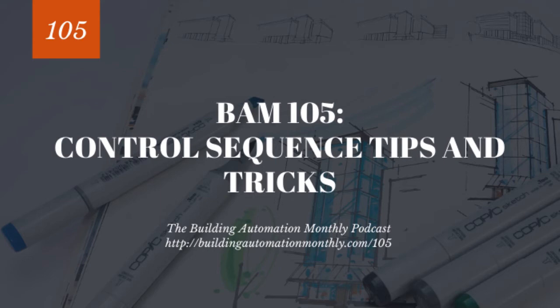However, with that being said, that is another reason why you would rearrange the sequence, but you're not changing the sequence. You're not changing the fact that you're enabling a chiller. An example of changing the sequence would be where you have an air handler whose discharge air temperature is reset maybe by box position. So you look at box position and you're resetting discharge air, or room temp, or whatever. And because of that, you have this discharge air reset. But you decide that you're just going to have a static discharge air temperature because you don't think resets work. And so you eliminate the reset. I've actually seen that happen quite a few times where folks are just like, yeah, they don't really need a reset. I know the operator of the building. They're just going to get confused, so I'm going to turn off the reset. And that is an example of completely changing the sequence. And that's what you want to try to avoid.